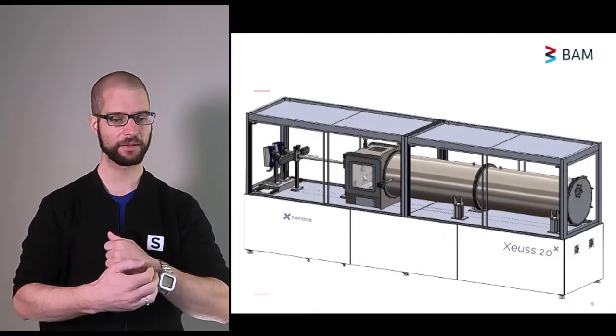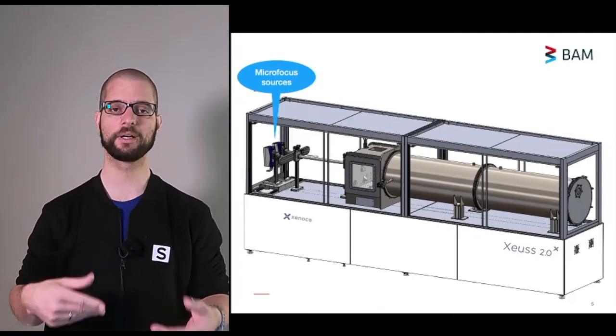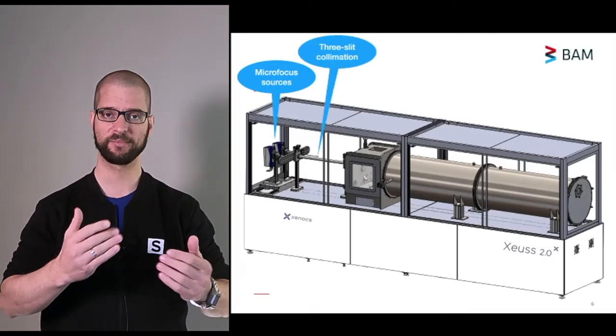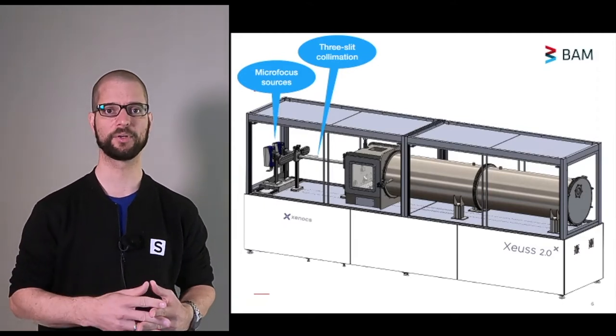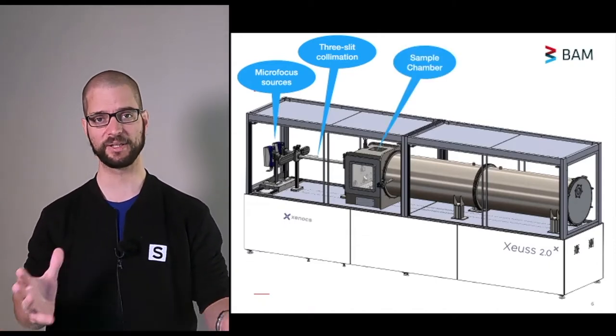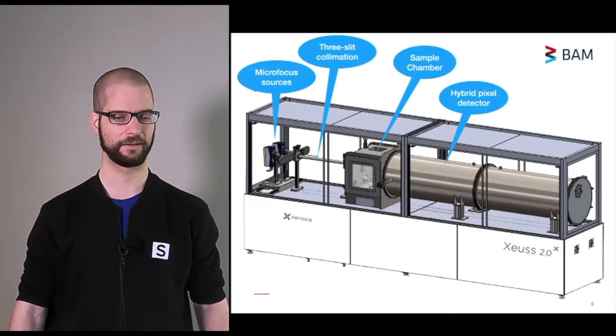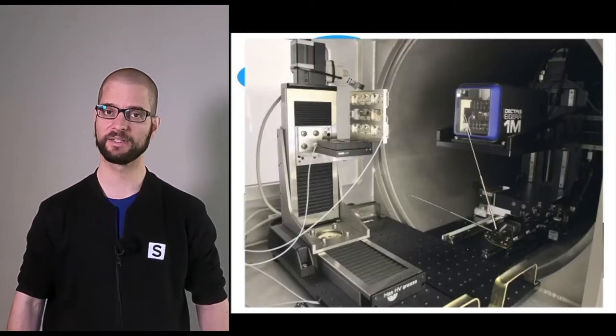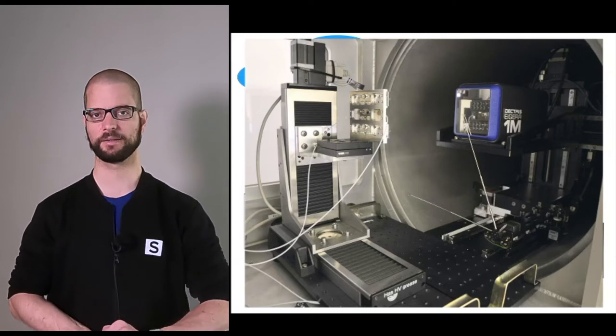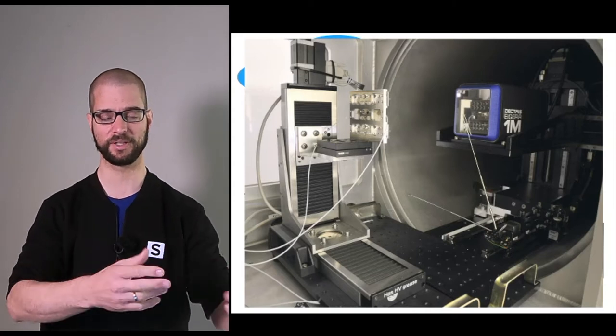The small angle scattering machines themselves are also not too complicated. All of them start with an x-ray source of one form or another, either a microfocus source or a synchrotron. A collimation section which cuts the beam down, in our case anywhere between 0.2 and 0.5 millimeters. We then have a very large sample chamber, in our case this is completely evacuated to reduce the background, and we have a hybrid pixel detector in a vacuum tank. We have a lot of space inside our sample chamber as well, just in case you want to try some nice in-situ experiments.